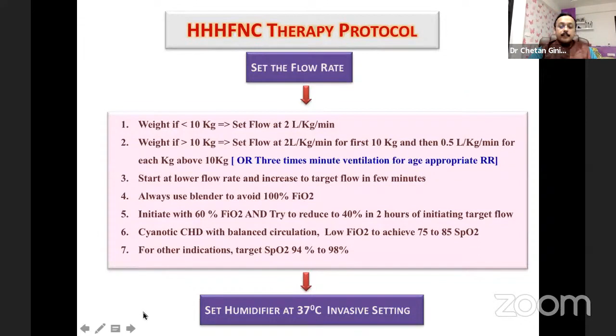There is always a blender. The HFNC or the Airvo with the Fisher and Paykel has a blender, so you just have to increase the oxygen rate, and it is measured on the display of the HFNC machine. Initiate usually with 60% FiO2 and try to reduce it to 40% within 2 hours after initiating and reaching the target flow. For cyanotic heart disease, we usually maintain saturations at 75 to 85. For other indications, our target should be somewhere around 94 to 98%. The humidification has to be set at around 37 degrees. By the time the heat reaches the nasal prongs, there is some loss of temperature, and it reaches around 34 degrees at the nares.